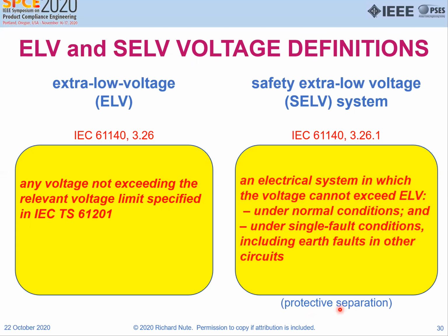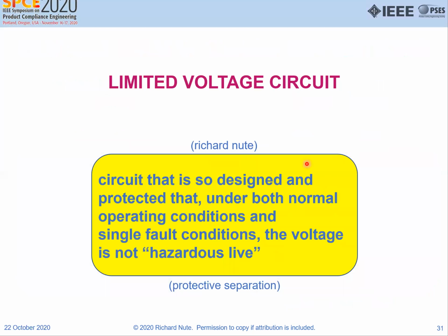It's got to have protective, in essence, protective separation between live parts and non-live parts, or between live parts and the subsystem. For the purpose of this presentation, I'm using the term limited voltage circuit, in order to contrast it with a limited current circuit, which is what we're after. So a limited voltage circuit is a circuit that's so designed and protected under both normal operating conditions and single fault conditions that the voltage is not hazardous live.